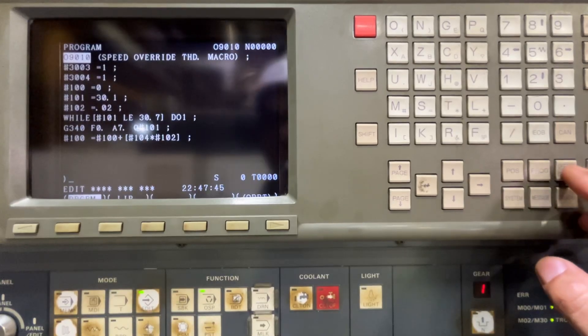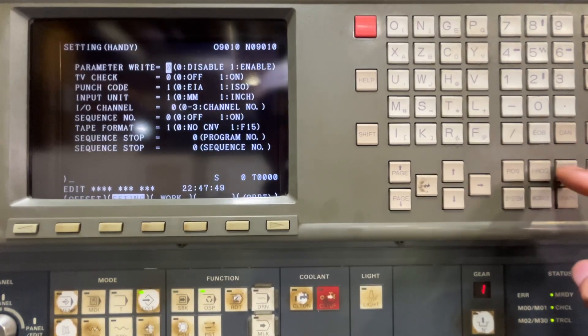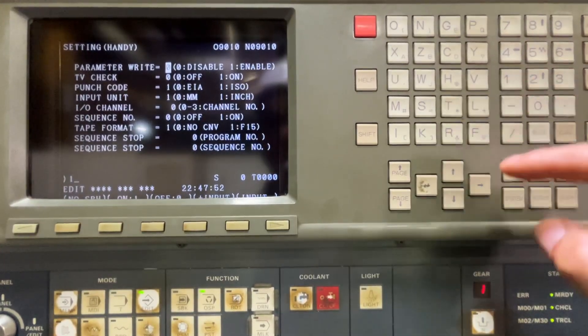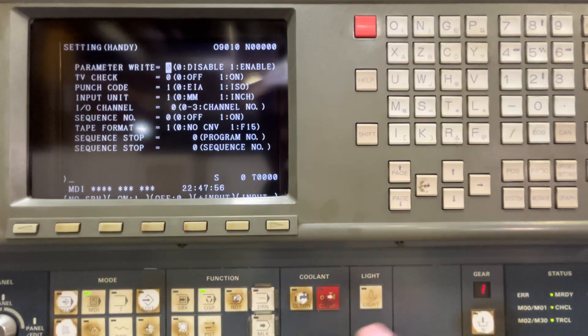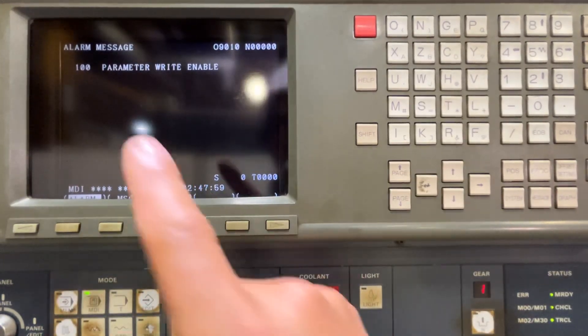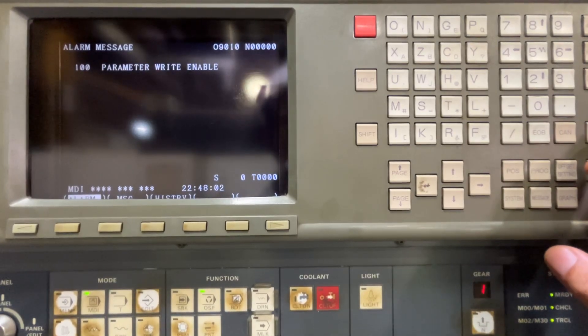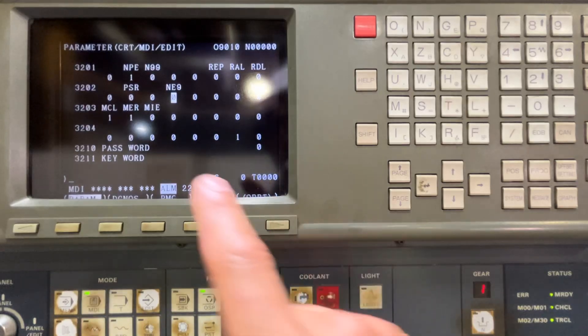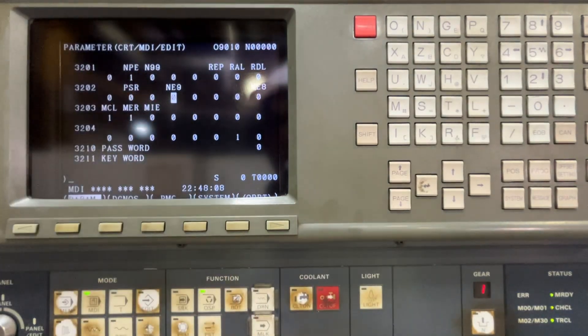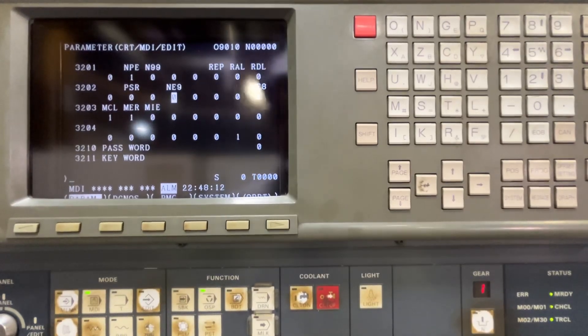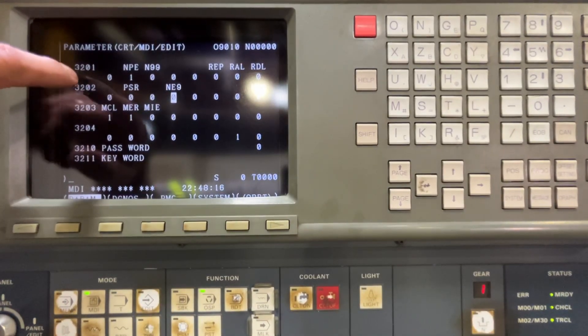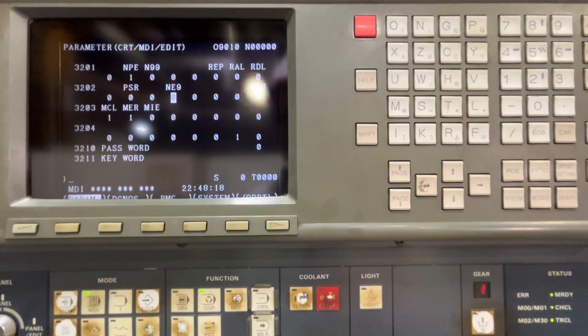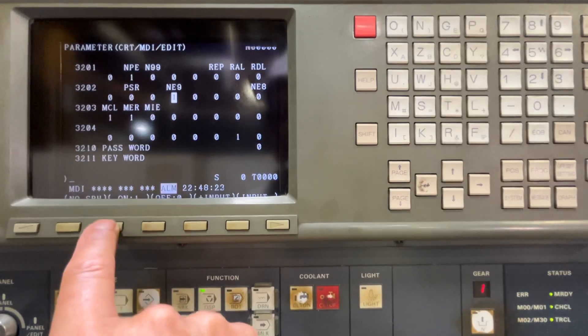And what I have to do is modify a parameter. So I'm going to enable the parameter write. I have to change to MDI and set to one that parameter. So now we have alarm 100. And in system, I'm going to change parameter 3202, which is bit number 4. So I'm going to set that parameter on.